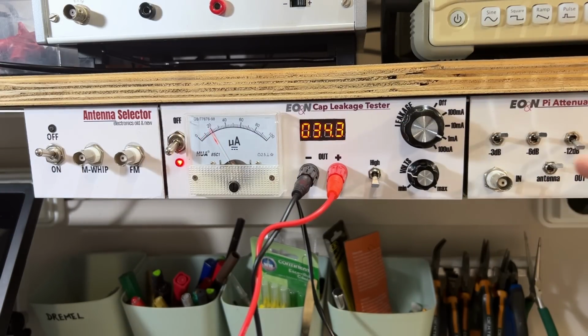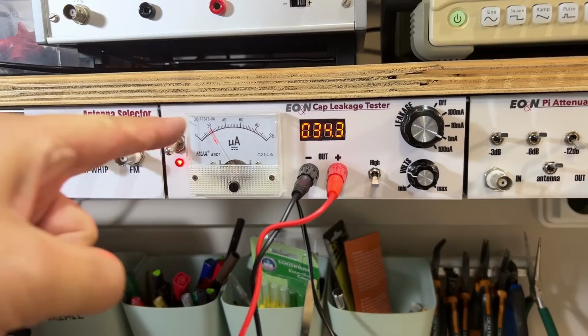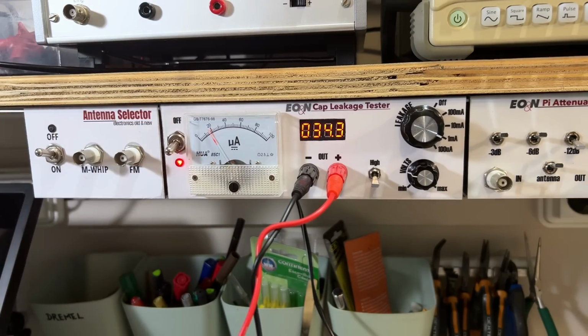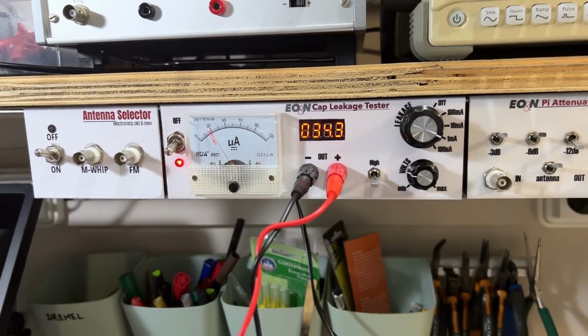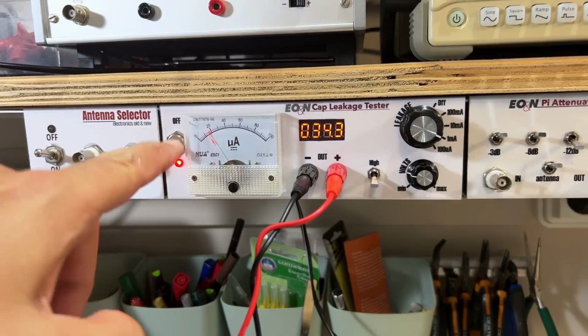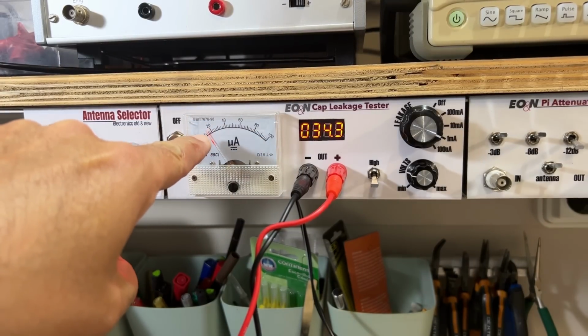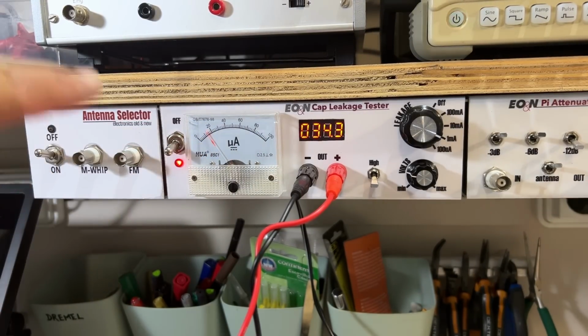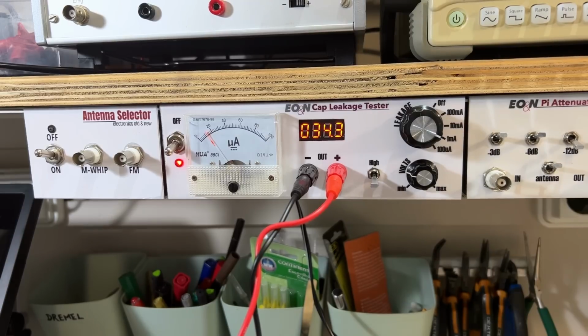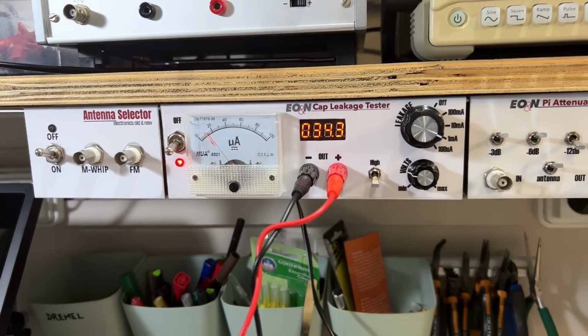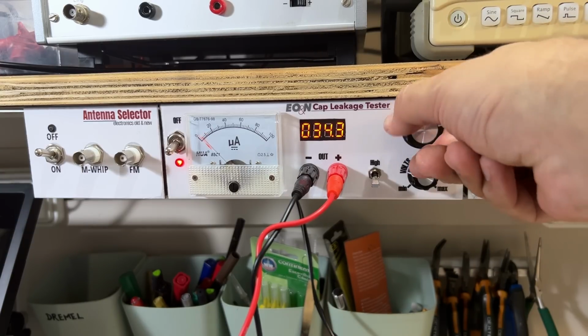I'm down to the 1 milliamp range, and it's actually leaking almost 200 microamps. Over time, if I leave this, I can actually see it coming down, coming down, coming down. That still seems to be quite a bit of leakage. It's coming down to close to 100 microamps.